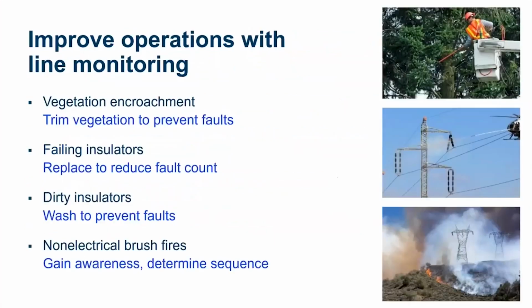We could dispatch crews, and maybe there's some overgrown vegetation that hasn't been mitigated. If we're seeing these waves launch, we might be able to get to that location and see, hey, the crews need to go out there and we need to trim trees or cut them down. Hopefully we can detect failing insulators, like the one we saw on the first slide when we started discussing traveling waves. If we can find a failing insulator before it actually causes a flashover, we can replace it and restore the line. Or if we've just got a dirty insulator, maybe there's been some contamination and we just need to clean it off.